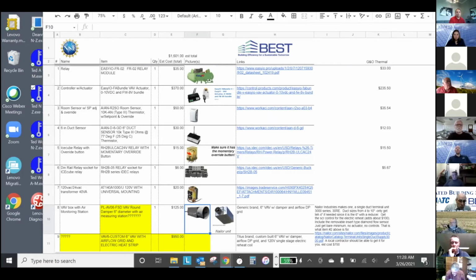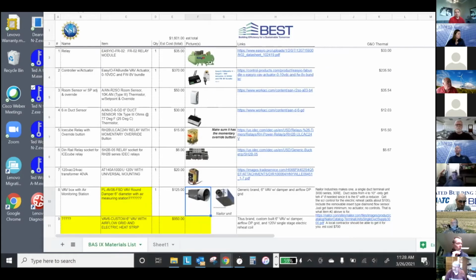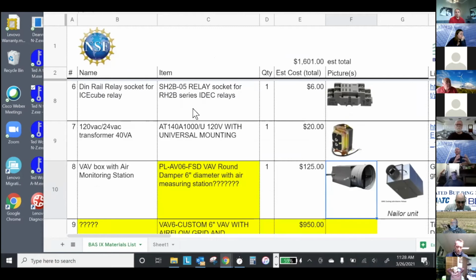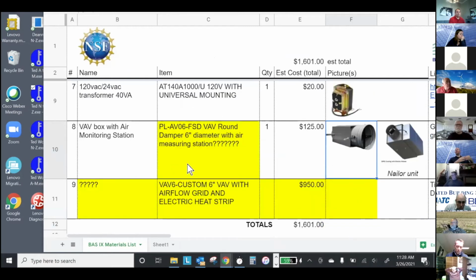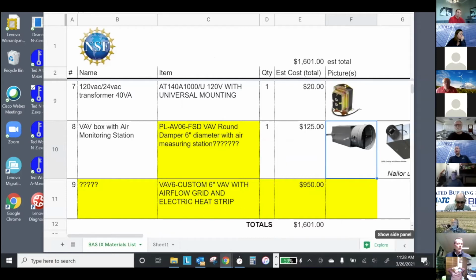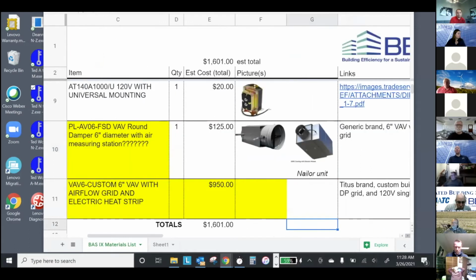The VAV box is the basis of what we're building upon. You only need one VAV box, not multiple. Ideally it has some form of modulating reheat — something we can send a 0 to 10 volt signal to, or 0 to 100%, so we get real modulation control. If you already have VAV boxes in your labs, that's great, you don't have to buy a new special one just for this workshop. The one thing we really hope you have is VAVs with reheat.